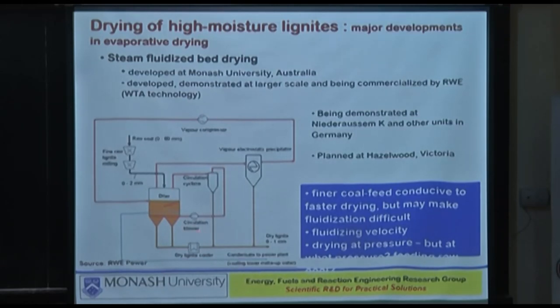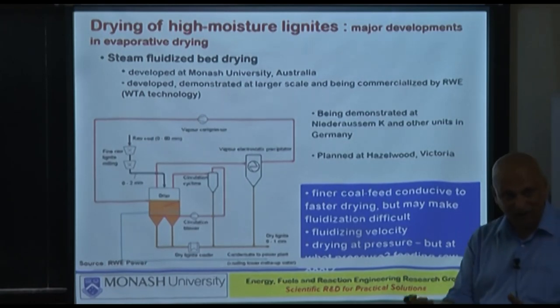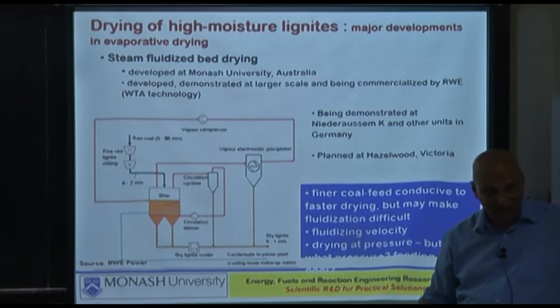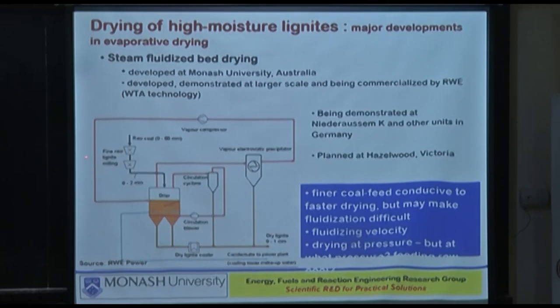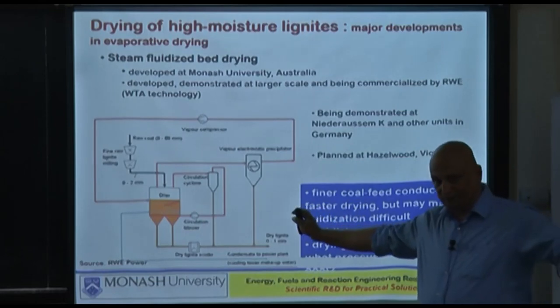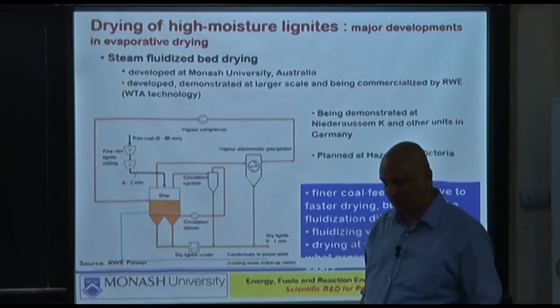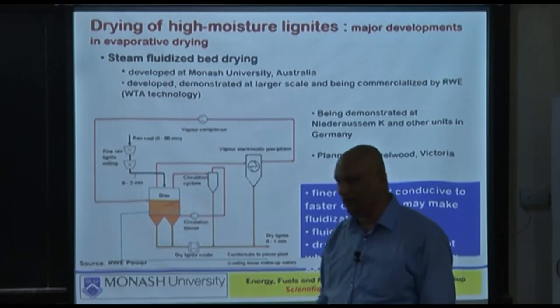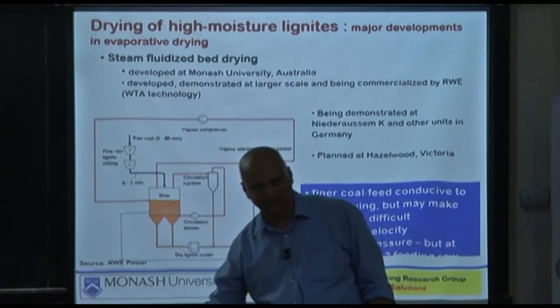So this is a blower because it is fluidizing steam only at 1 bar, coming from 1 bar to 1.1 bar. So that's why it is called blower. Here it is called compressor because it's compressing the water vapor from 1 bar roughly to 5 bar or so. So there's a difference, but everything is closed. You're not getting anything from outside. You're not requiring anything from outside.